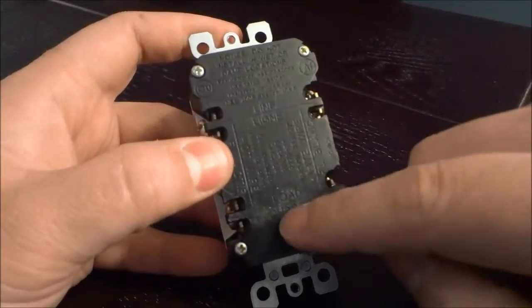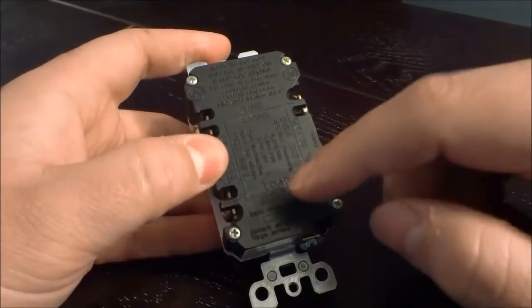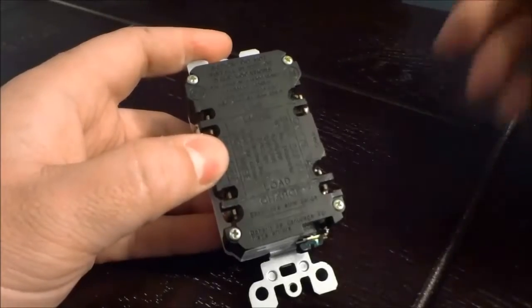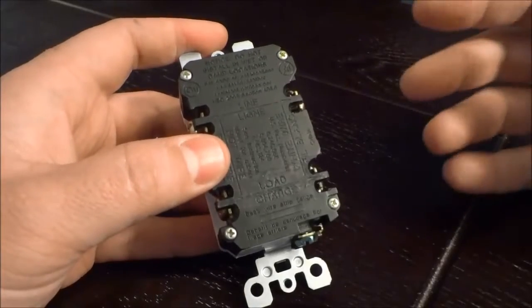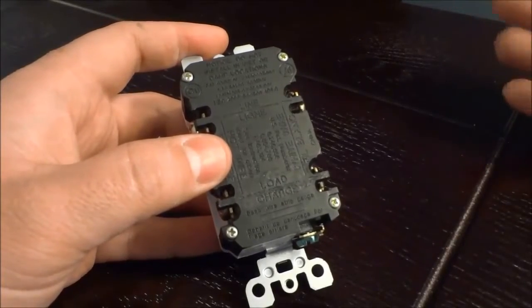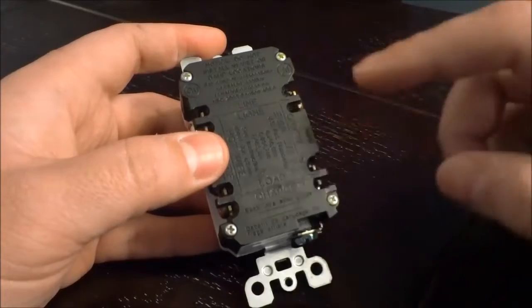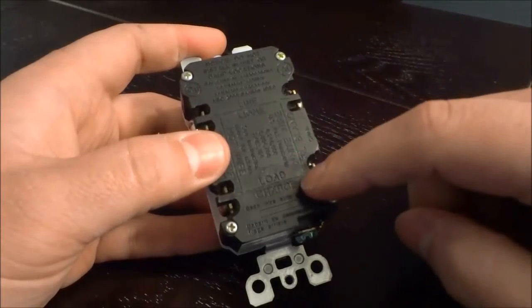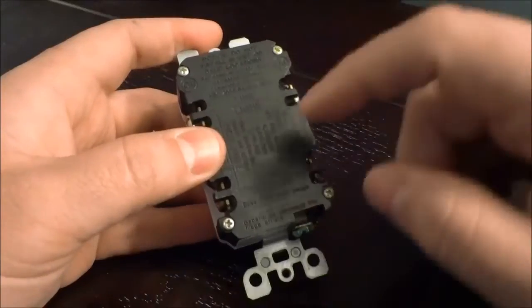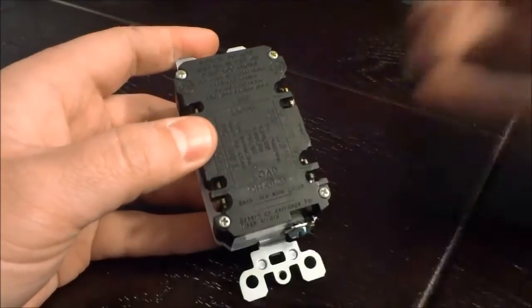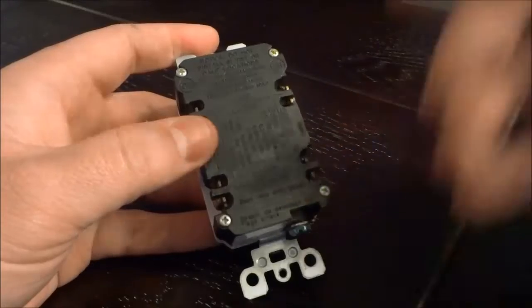Now the load is for power that is going out after the GFCI receptacle. So if you had a few other outlets or receptacles that were connected after the GFCI—with regards to the circuit after the GFCI—then you would connect the next set of electrical wires to the load.